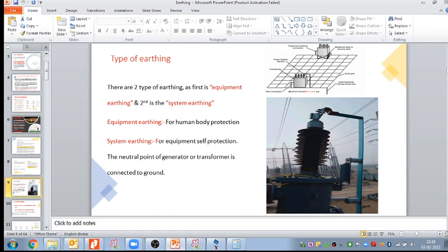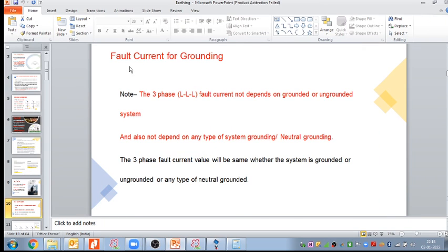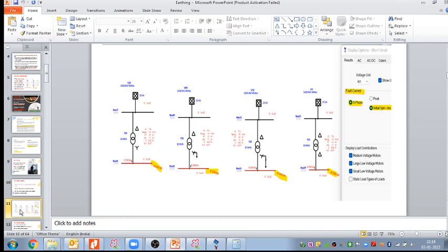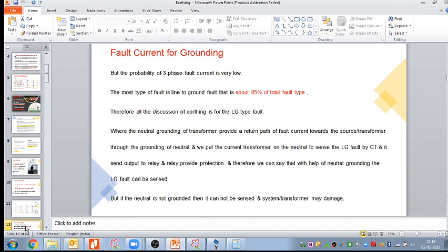Okay, now the types of earthing we discuss: first, system earthing, and second, equipment earthing. In system earthing, which is for equipment protection, the neutral point of the generator or transformer is connected to the ground, and in that case the three-phase fault current will not link with the neutral grounding or system. This will remain the same. This is the example that we have taken, right?